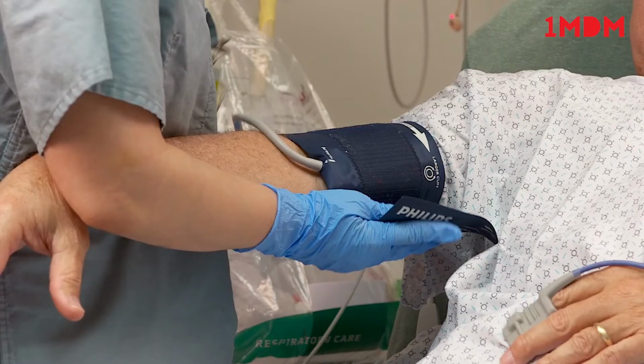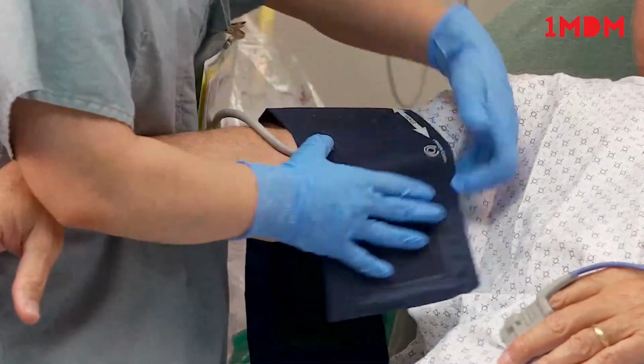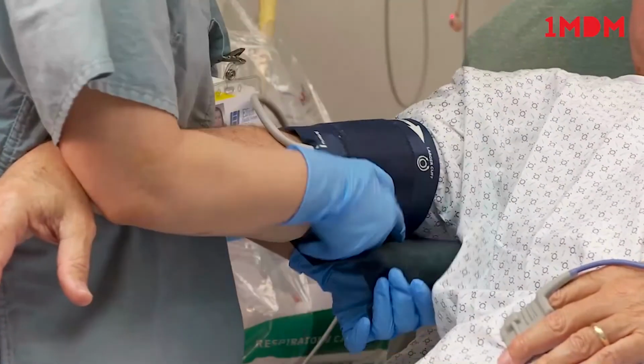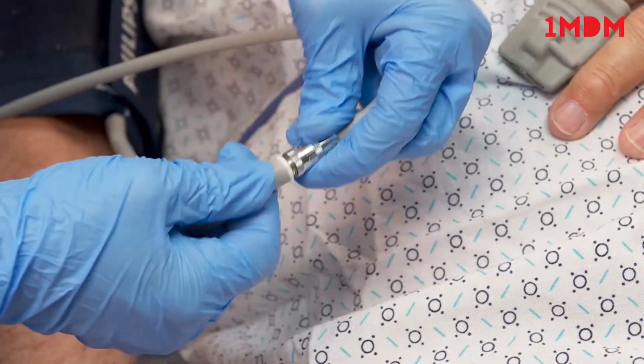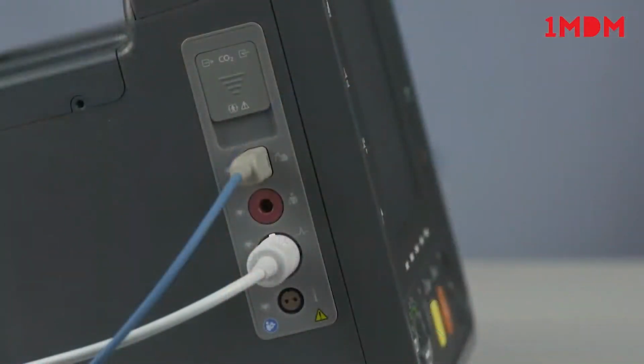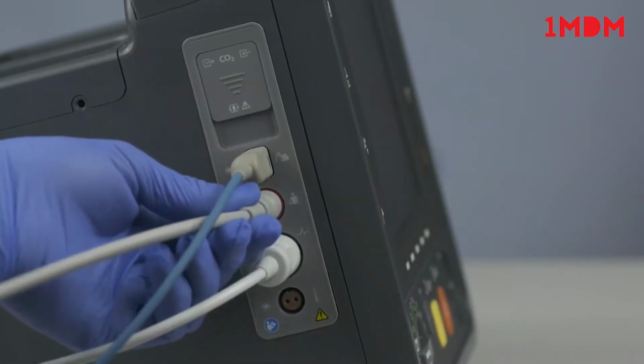The first step is to select the appropriate sized cuff for the patient. The cuff width should be either 40% of the limb circumference or 2/3 of the upper arm length, and the inflatable part of the cuff should be long enough to encircle 50 to 80% of the limb.